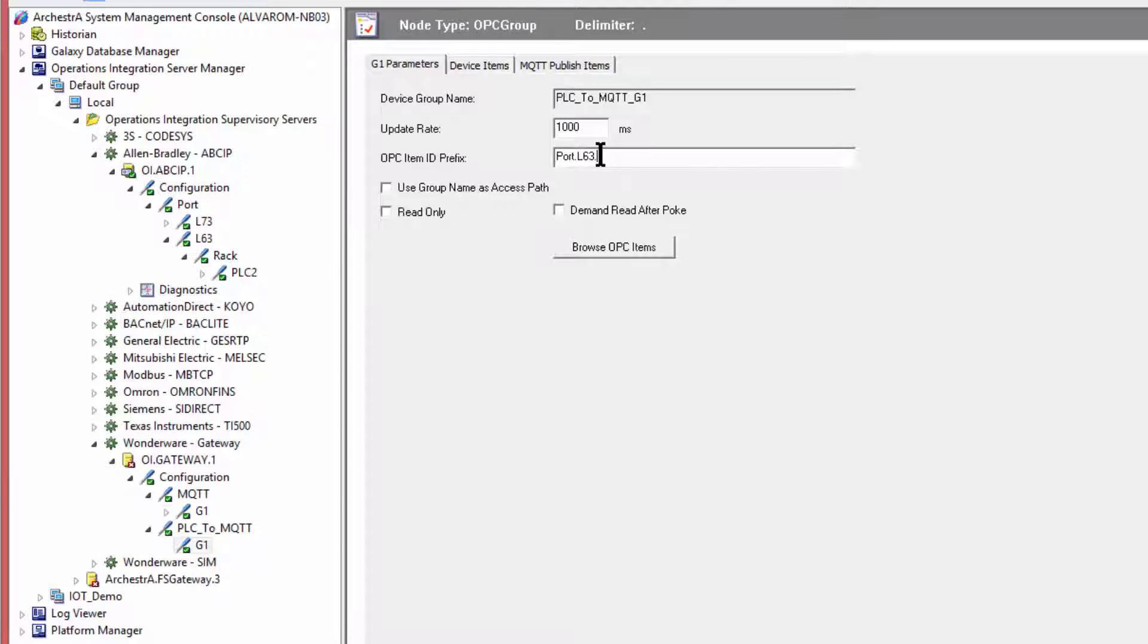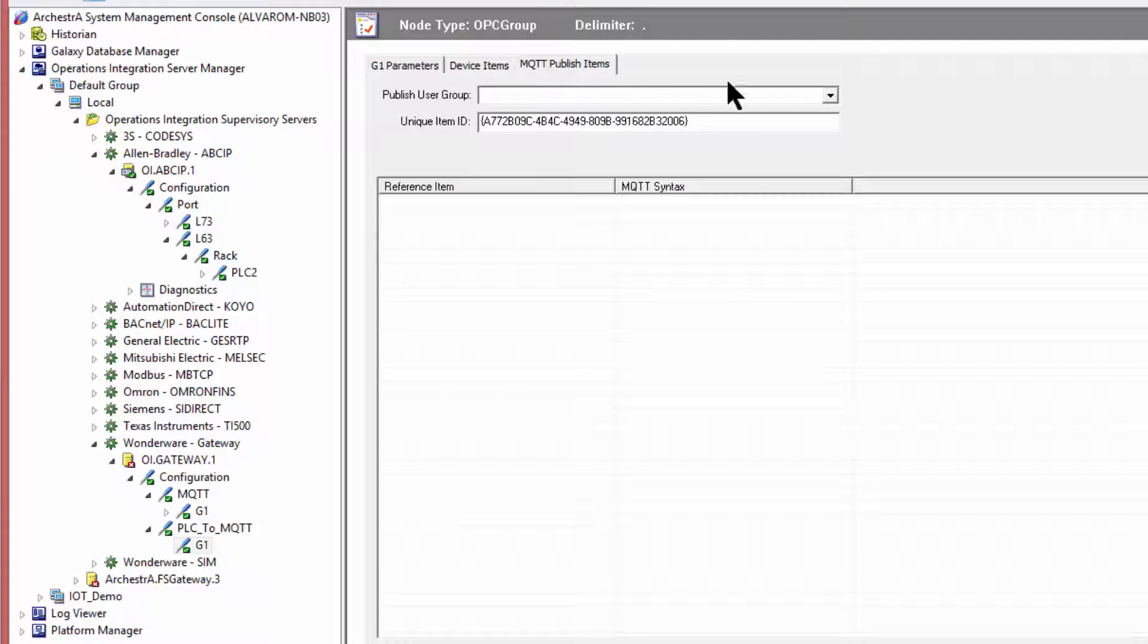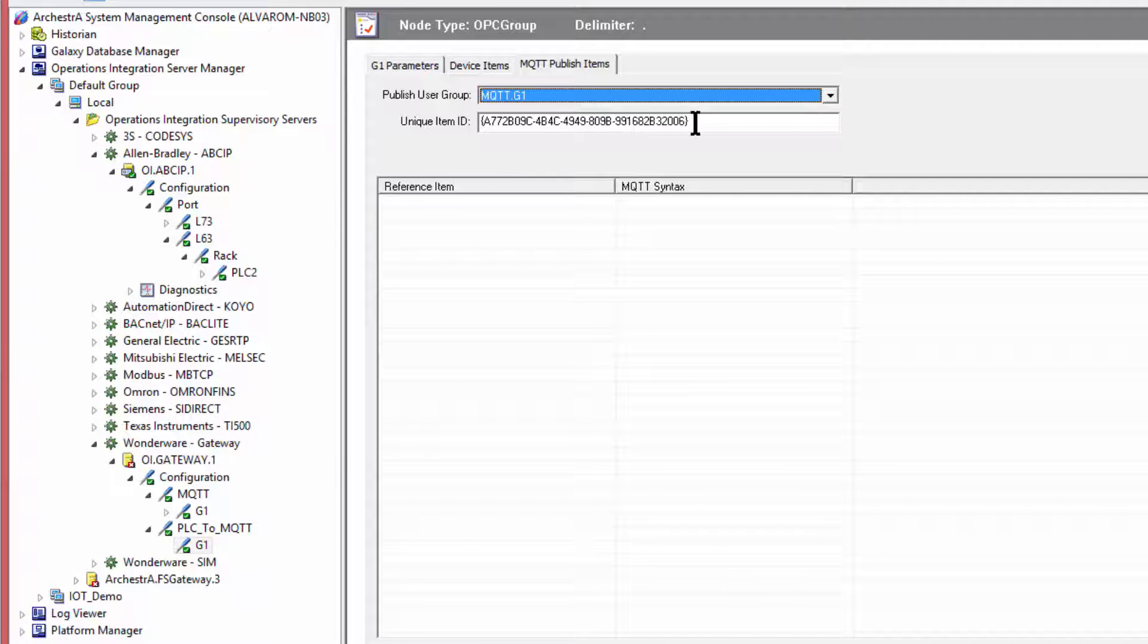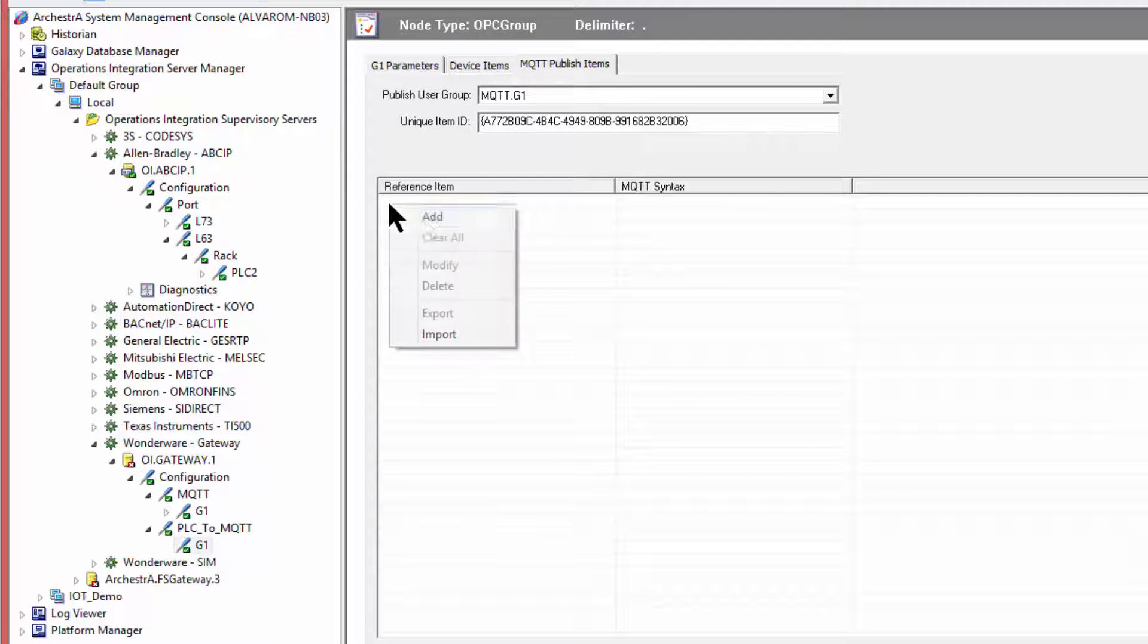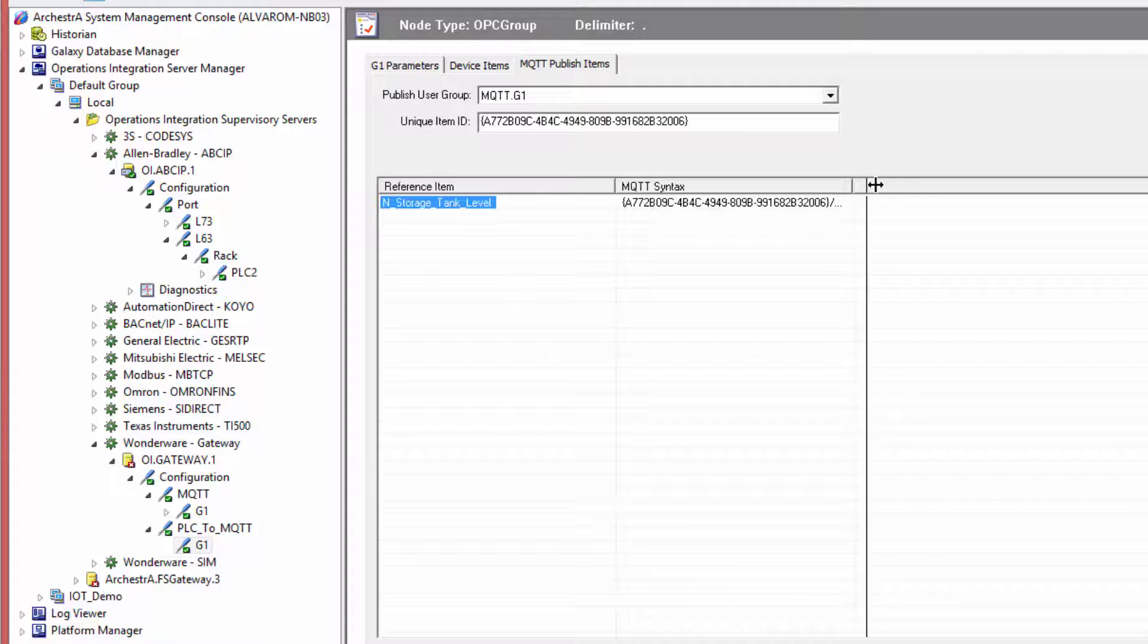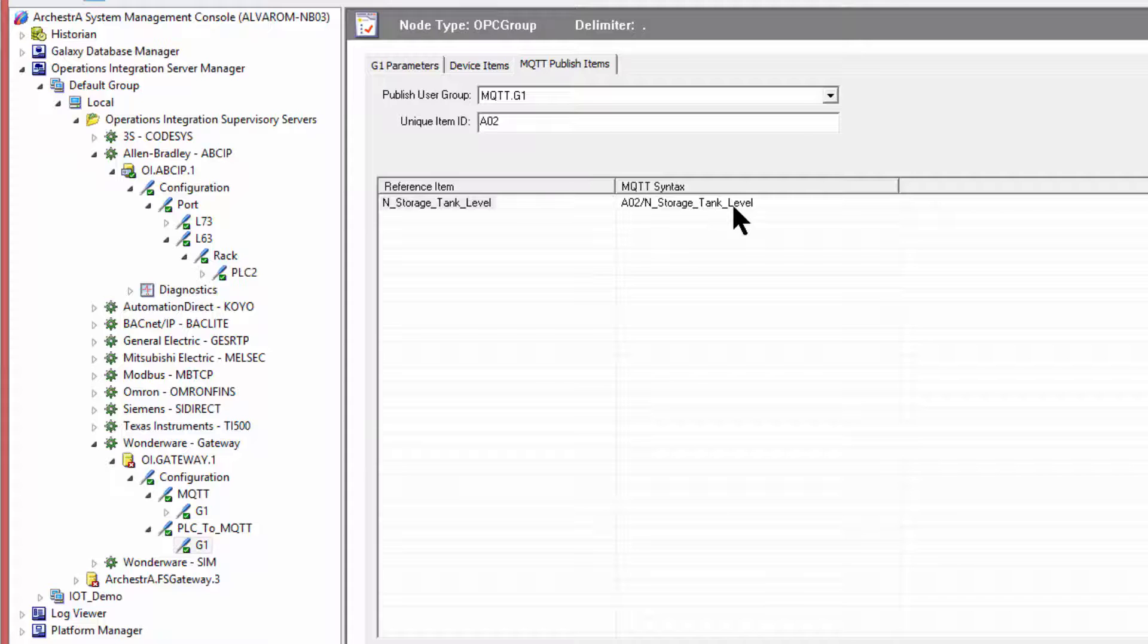And now, you also see a new tab on the top called MQTT publish items, which is where exactly we put those specific tag names that are going to be used to publish. We link to that MQTT broker connection that we used. And also, we have a uniqueness ID because as we create tags, it is possible that these remote systems are all identical. So when they go to a central MQTT broker, we don't want that information to be mixed. Hence, the need for the uniqueness ID. You can simplify this uniqueness ID for something that makes more sense to you. And that's all you need to do.